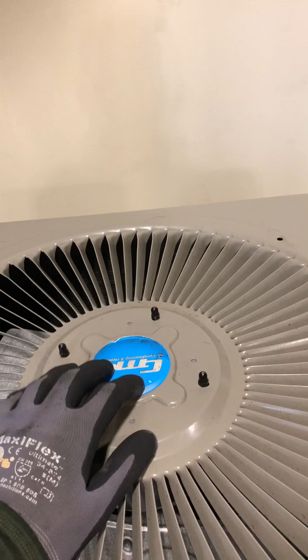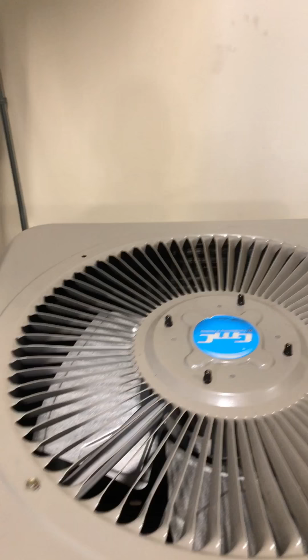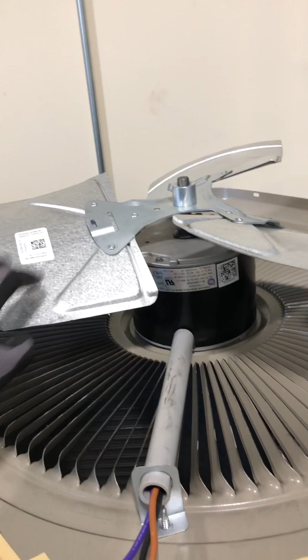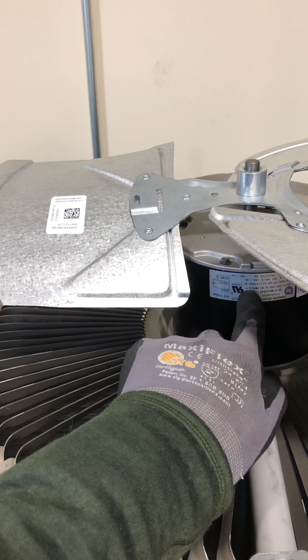We're going to have a condenser fan motor. Big electrical, lots of electrical problems happen with these. These are a very common failure. In order to get to it, a lot of units are different - sometimes the center part will just pop out, but in this case I have to take off the whole top and flip it over. I've actually taken one off over here so you guys can see what that looks like. We just flip it upside down - pretty basic fan blade, single speed motor most of the time.